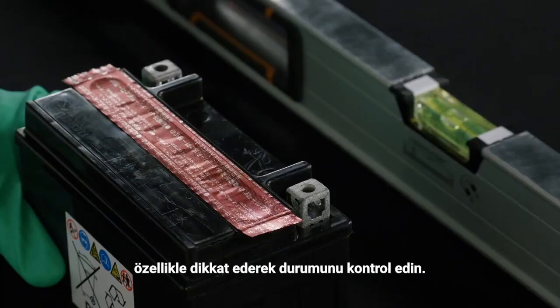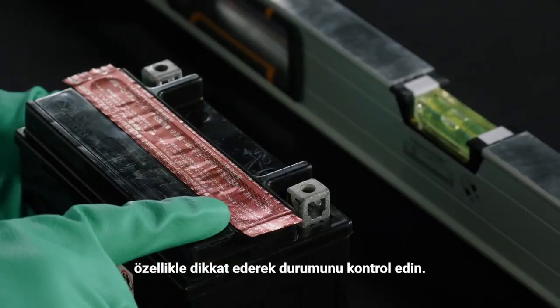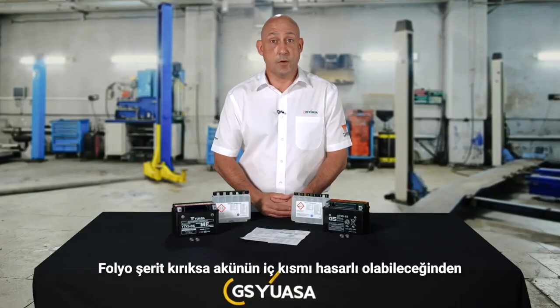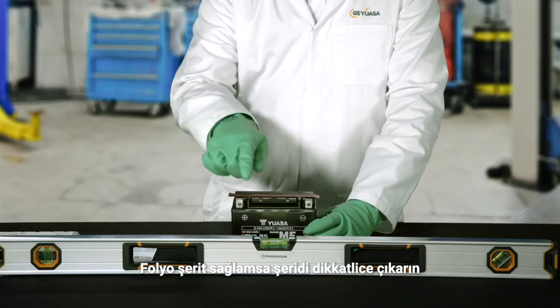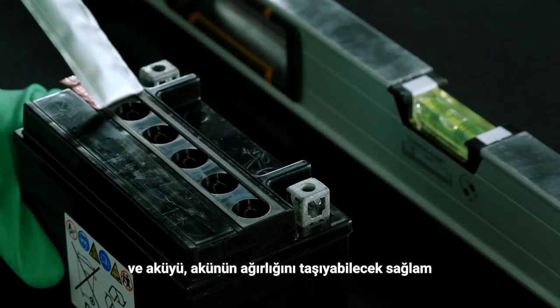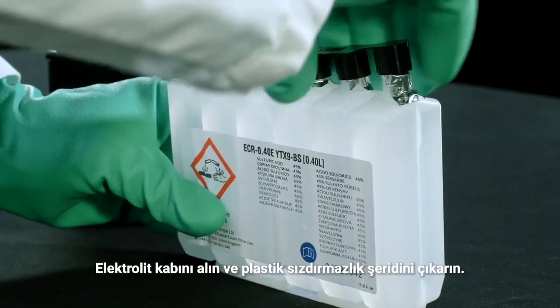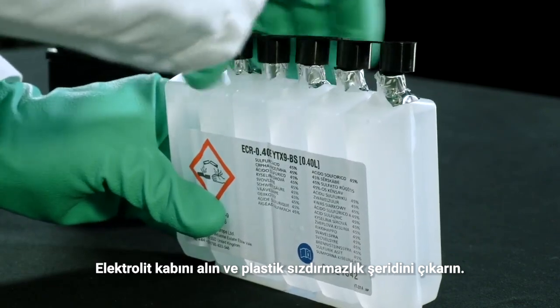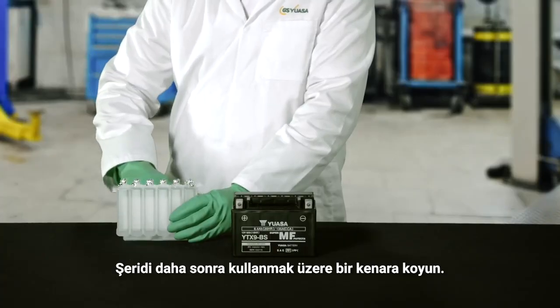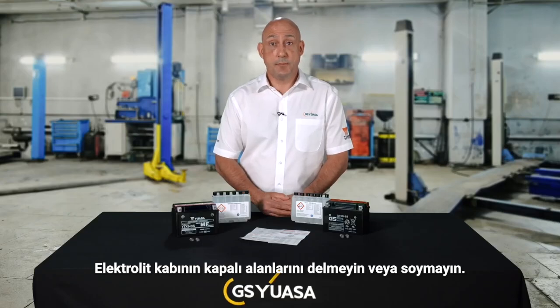Remove the battery from its packaging and check its condition, paying special attention to the foil strip covering the filling ports. If the foil strip is broken, do not commission, as the battery may be damaged internally. If the foil strip is intact, carefully remove it and place the battery on a solid, flat, level surface that is capable of supporting the battery's weight. Take the electrolyte container and remove the plastic sealing strip. Put this aside for use later. Do not pierce or peel the sealed areas on the electrolyte container.